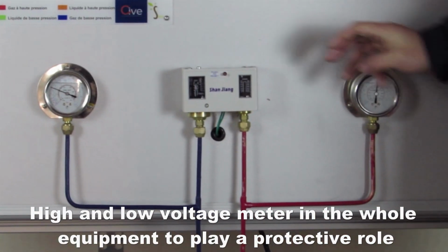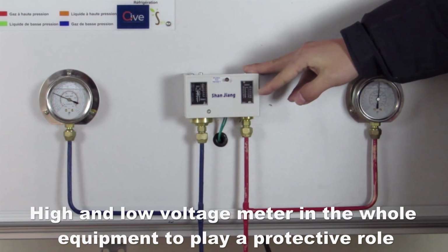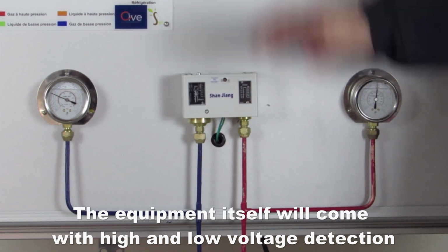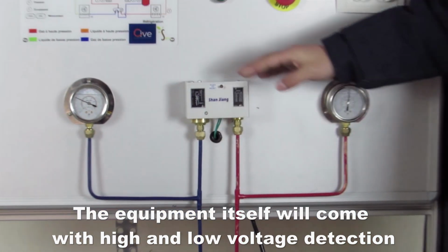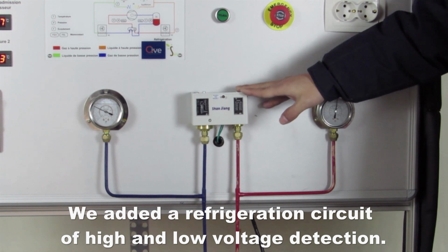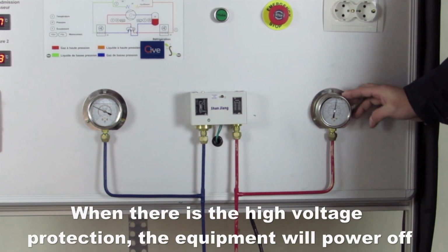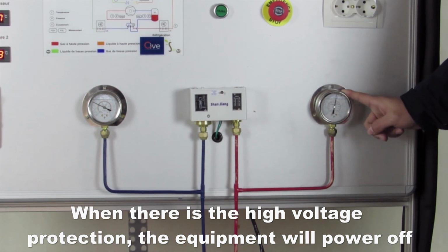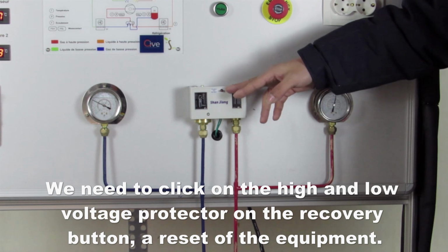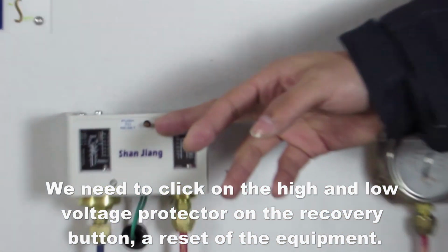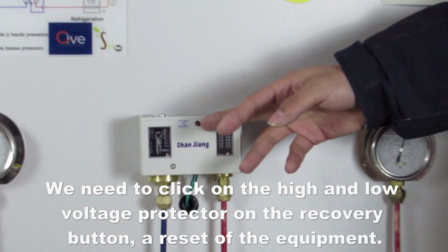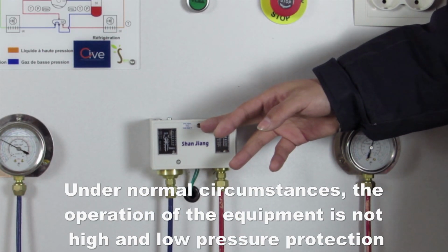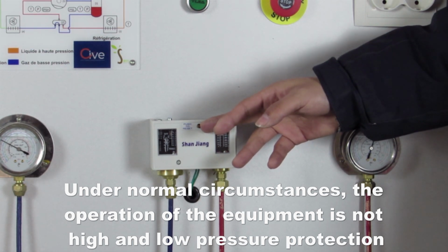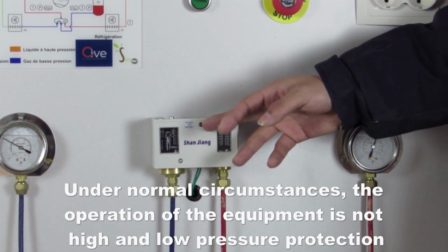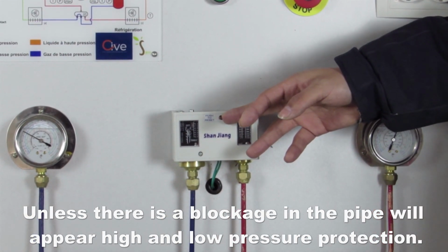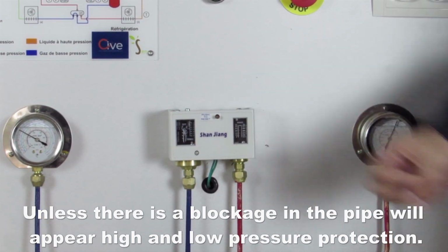The high and low pressure meter plays a protective role in the whole equipment. The equipment itself will do high and low voltage detection. We added a refrigeration circuit of high and low voltage detection. When there is high voltage, the equipment will power off. We need to click on the recovery button on the high and low voltage protector to reset the equipment. Under normal circumstances, the operation of the equipment does not trigger high and low pressure protection, unless there is a blockage in the pipe.